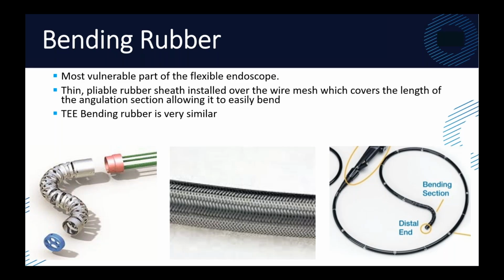And this chainmail section is the same kind of piece that runs through the entire insertion tube. So that's kind of there underneath that vinyl the whole way. But what's different here is that we no longer have those layers and layers of vinyl covering that insertion tube. When we get to the bending rubber, it is one piece of rubber tubing about that long, and it is a couple millimeters thick. It has to be super flexible. So this is the weak point. This is the point that is so easy to have a problem. And we'll see several pictures of this.